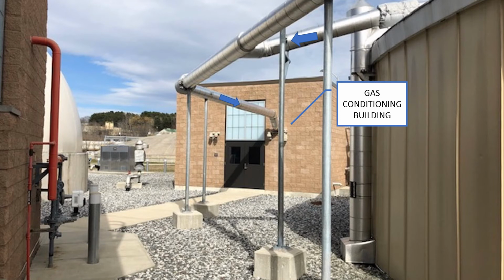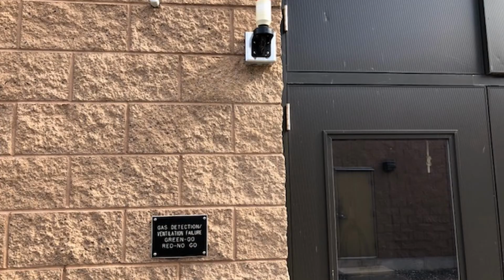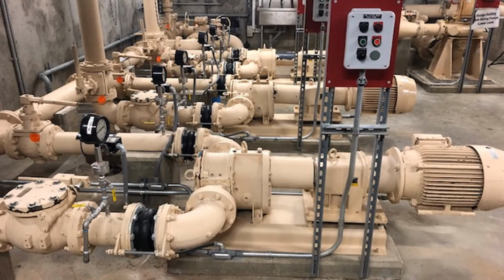You can see that as the gas flows off the top of the digesters, the two digesters are combined before entering the gas conditioning building. Because the biogas can be explosive, we have some gas detection within this building. That gas detection system is tied into lights on either side of the door. The green flashing light tells us it's safe to enter. The red light tells us we cannot enter until the gases have been removed from the space. The pumps here are the screw press feed pumps.